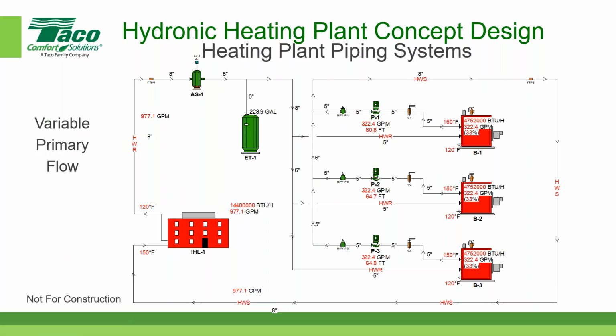Yep. So let's do the test here, Brett. Let's make sure that we didn't mess up when we did this calculation. So it's 14,400,000, divided by 30, divided by 500, and the GPM should come out to 960. Oh, I know why it's 977. The reason it's 977 is because the software does the calculation based on the mass rate of flow in pounds per hour, and then it converts it into gallons per minute when it displays the actual value. So in other words, it adjusts for the expanded water temperature. Does that help? Excellent answer.